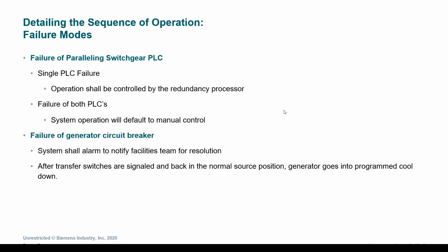In the case of a failure of a generator circuit breaker, which again would be very rare, the system would again alarm and notify the facilities team for them to get involved and resolve the situation. Once the transfer switches are signaled and back in the normal source position, the generator would go down to its normal programmed cool down.